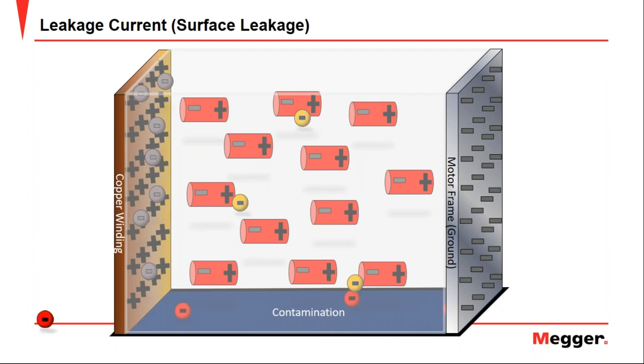And finally, we have the leakage current. This current is the one that circulates through the contamination of the insulation and increases as the insulation is more degraded or aged. At the end of the day, this is the current that we are interested in measuring in order to calculate the insulation resistance, since this current is indicative of the insulation system condition. The main characteristic of this current is that it is constant over time. It will not vary as a function of time. So, after a certain period of time, and taking into account the behavior of the other currents, the leakage current will be the only relevant one in the circuit.